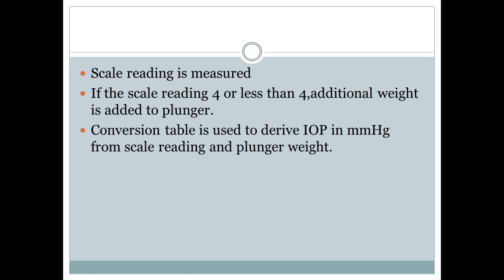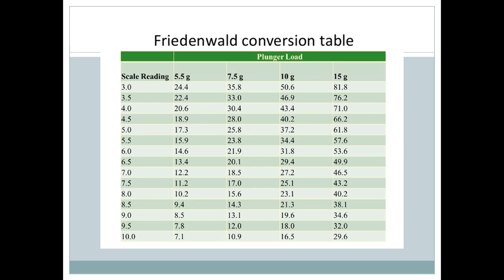For converting those grams into IOP in mmHg, you have to use the Friedenwald conversion table. I'll show you how to convert it. Suppose your instrument is using 5.5 gram and your scale reading shows 5.5, which means you are not adding any additional weight, so your IOP will be 15.9 mmHg. And suppose after adding weight your reading shows 5.5, then 23.8 mmHg will be your IOP.